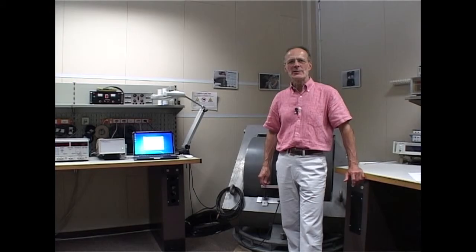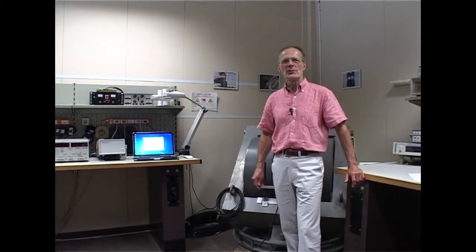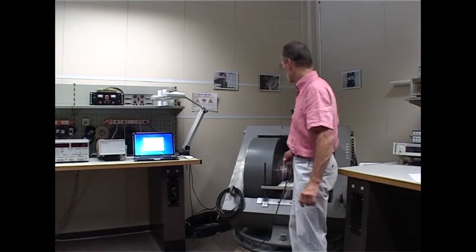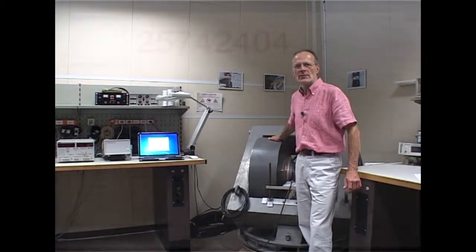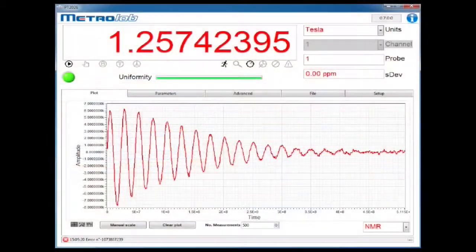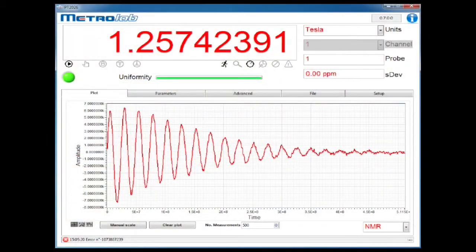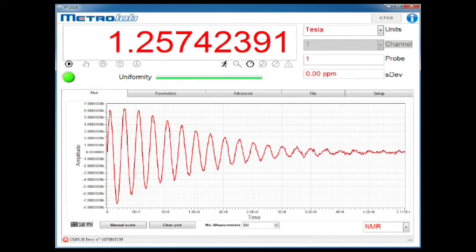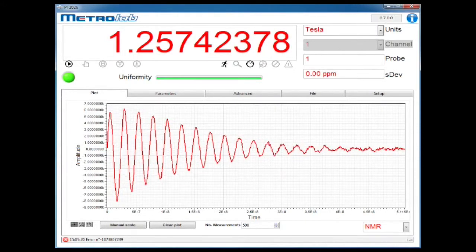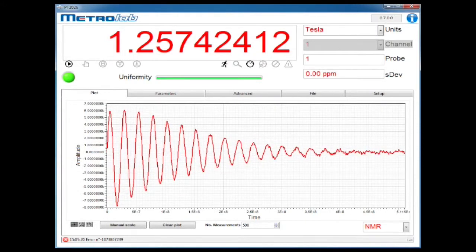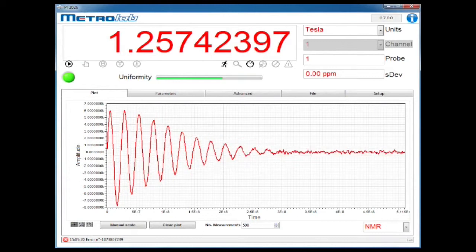Now let's move to a slightly larger magnet, our 2-ton lab magnet at about 1.25 tesla. We immediately observe a major improvement with a nice long NMR signal, good uniformity, and excellent standard deviation.